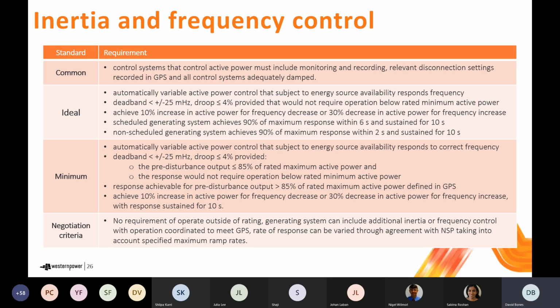And additionally, there's also requirements about achieving a 10% increase in output in response to frequency reduction and a 30% reduction in response to a frequency increase, and for that to be sustained for 10 seconds. So that requirement's somewhat similar. What's been relaxed is the speed with which you have to get to those response levels. There's common requirements for this one as well. And there's also a set of negotiating criteria as shown on the slide.